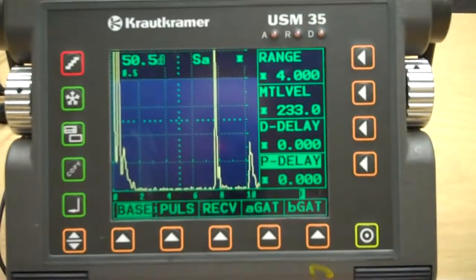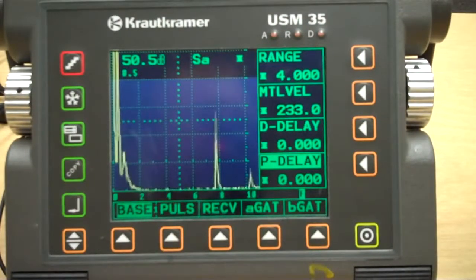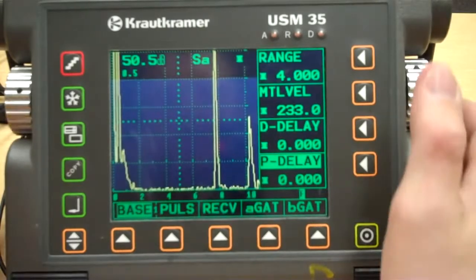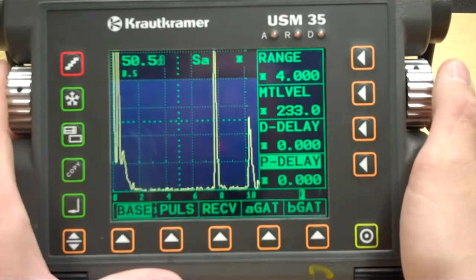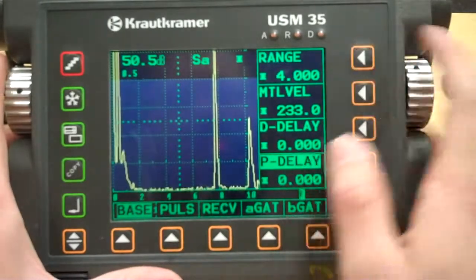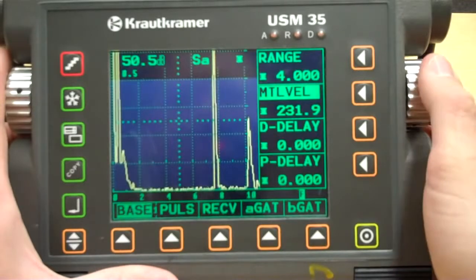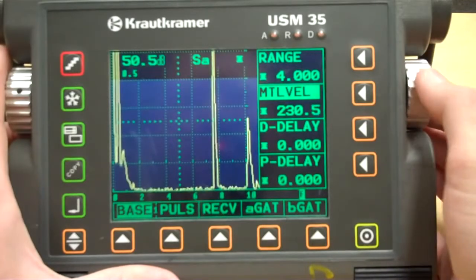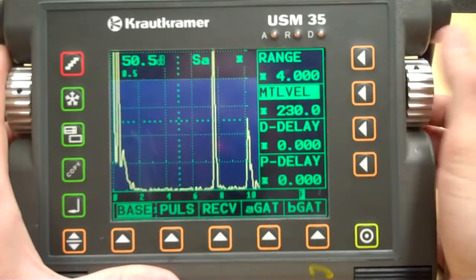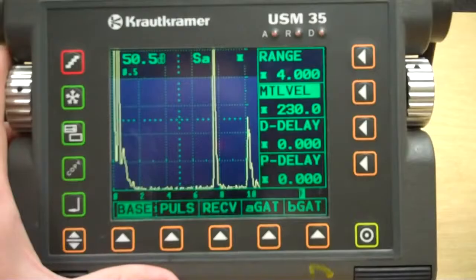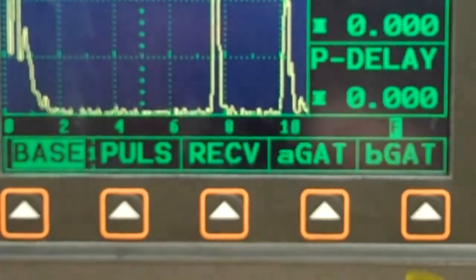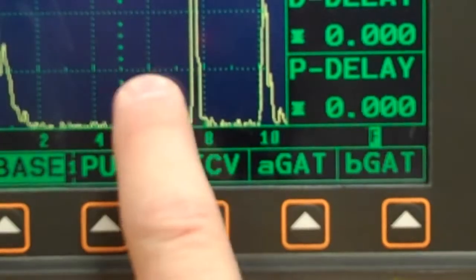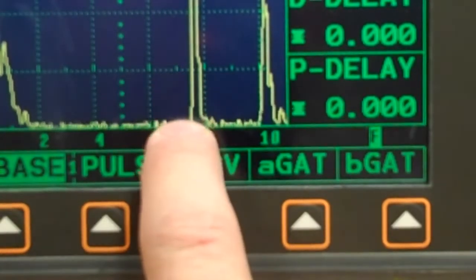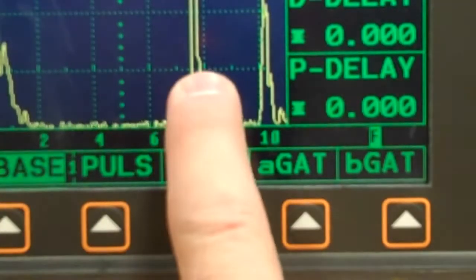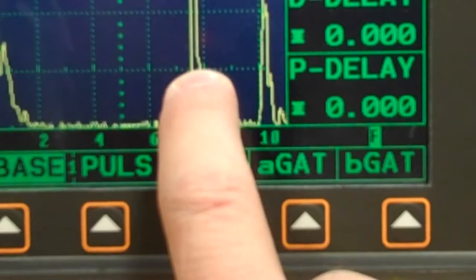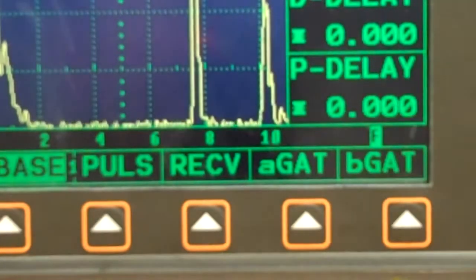Okay, so here we are. If we're on a 3-inch test block with a 4-inch range, then our 3-inch signal should be coming up at about 75% screen width. I'm out of it today. So let's change our velocity here just a little bit. That was that 233 thing that we were piddling with earlier. And I would say right at 230, if we can zoom in and you can take a look at where this thing's breaking the baseline, you can see we've got our 60, 70, 80%, so we want to be pretty much right in the middle, but you see it takes a little bit of a jag right there. So we're coming up just shy of 76% once we cross that first line. So I'm going to call that 75.